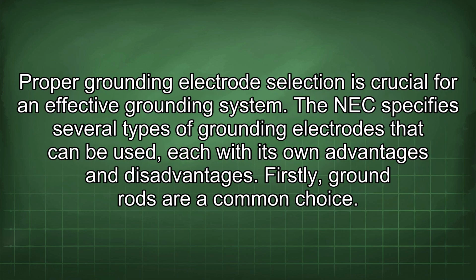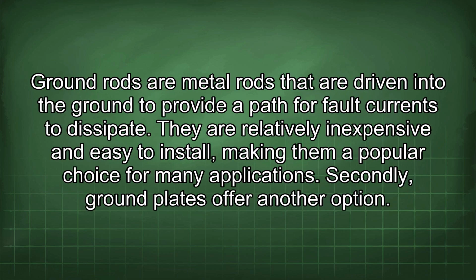Proper grounding electrode selection is crucial for an effective grounding system. The NEC specifies several types of grounding electrodes that can be used, each with its own advantages and disadvantages. Firstly, ground rods are a common choice. Ground rods are metal rods that are driven into the ground to provide a path for fault currents to dissipate. They are relatively inexpensive and easy to install, making them a popular choice for many applications.